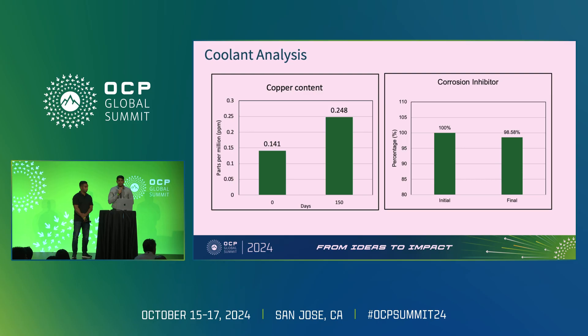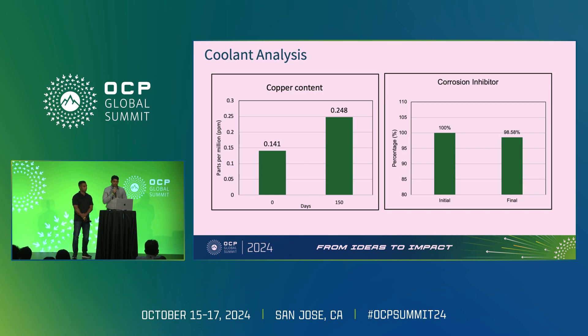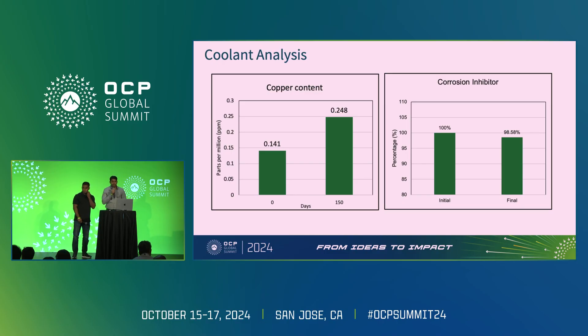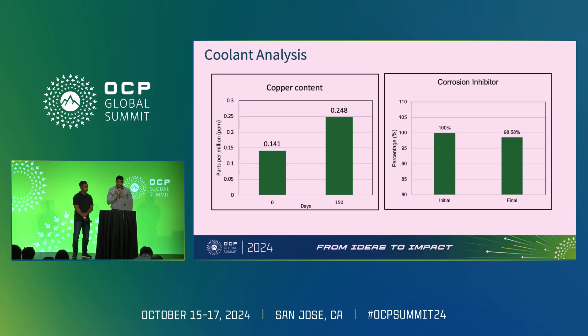Next is the coolant analysis. Coolant samples were collected every 30-day interval from the test setup, and we made comparisons for different parameters at day zero and the final day of analysis. For the copper content — where the main source would be the cold plate — at day zero the baseline sample had a copper content of around 0.141 ppm, which is almost 141 parts per billion inside the coolant. At the end of testing there was a small increase to 0.248 ppm, corresponding to 248 parts per billion. This is a very small increase and is within the recommended standards of the vendors, which typically flag copper content increases above 3 to 3.5 ppm as requiring critical measures to replace the coolant.